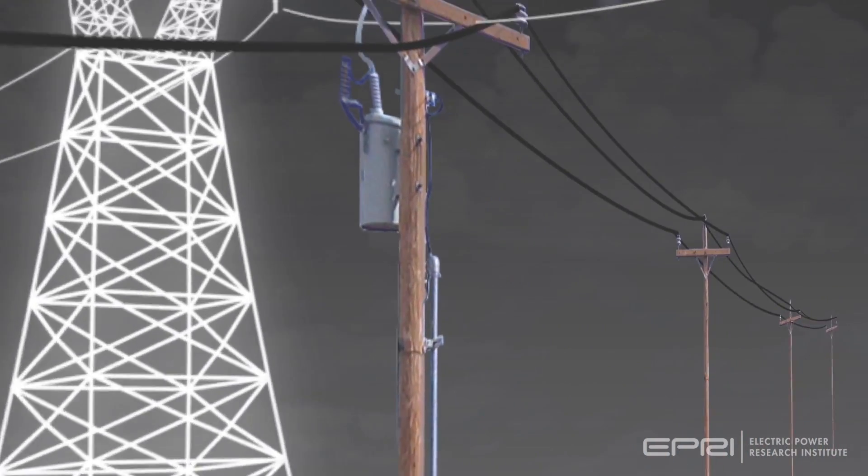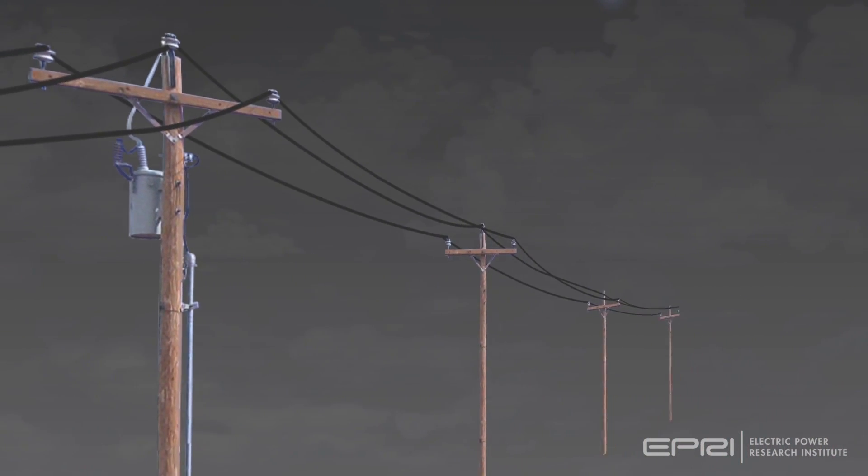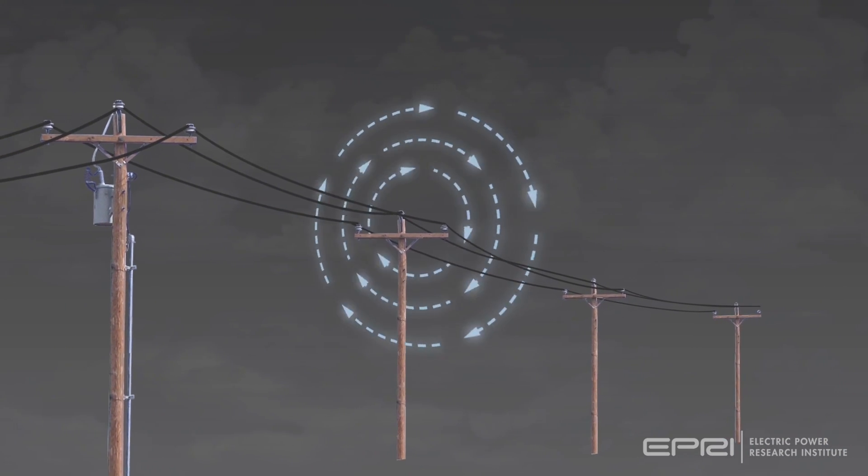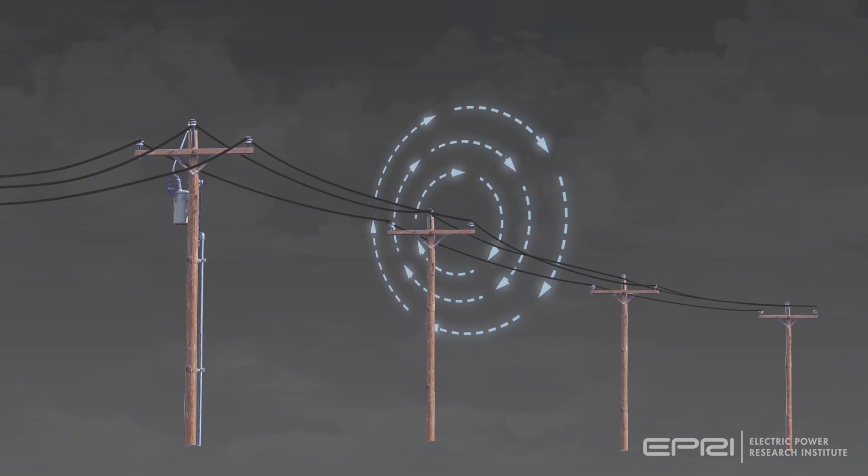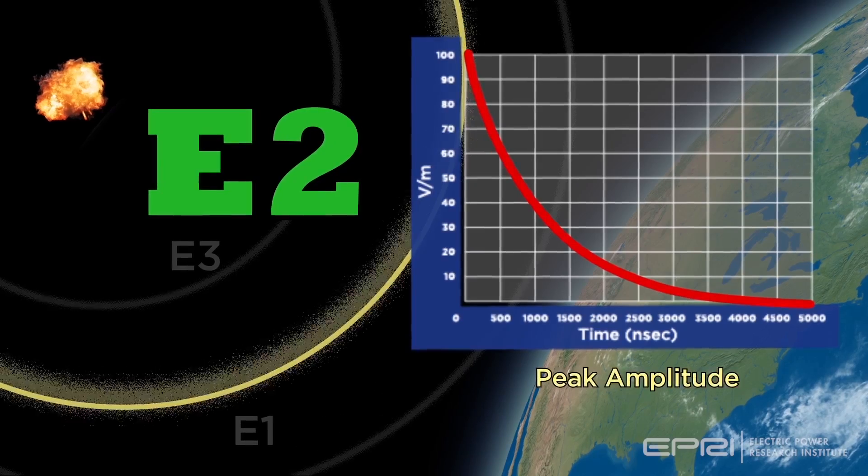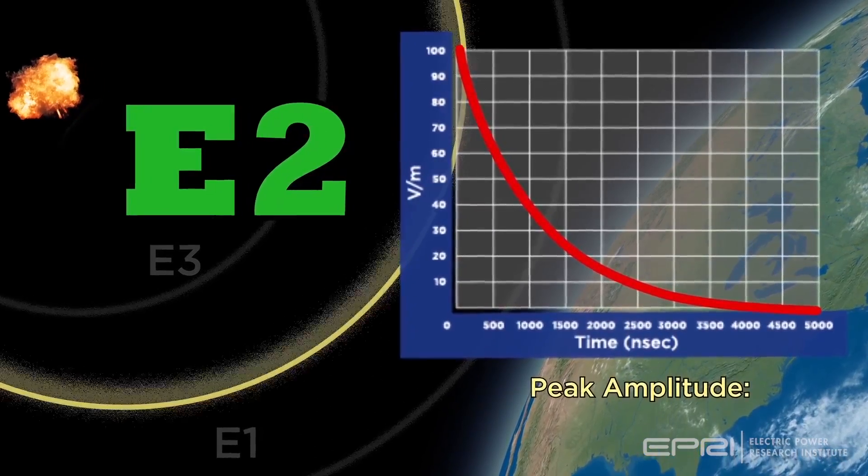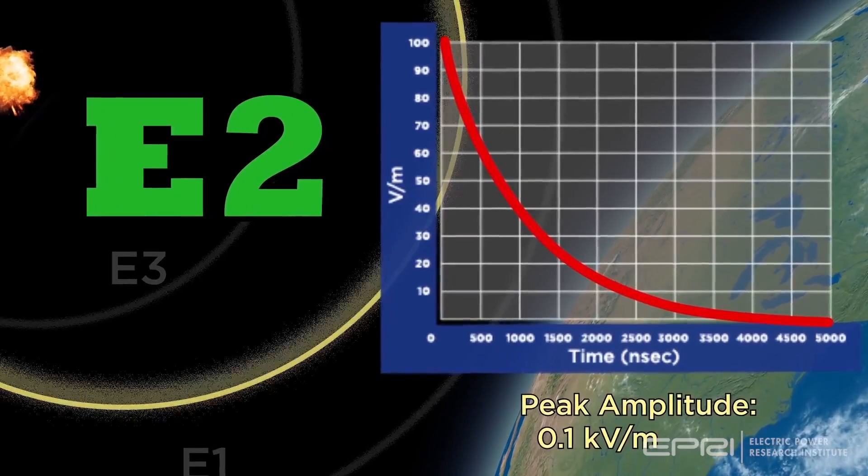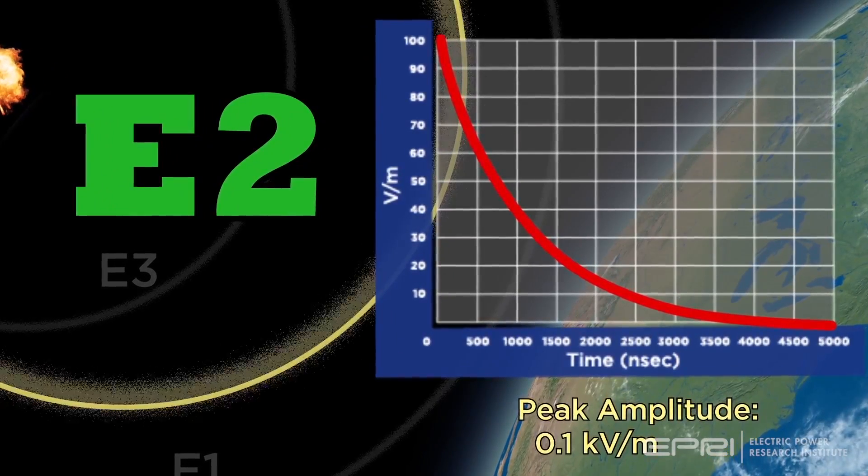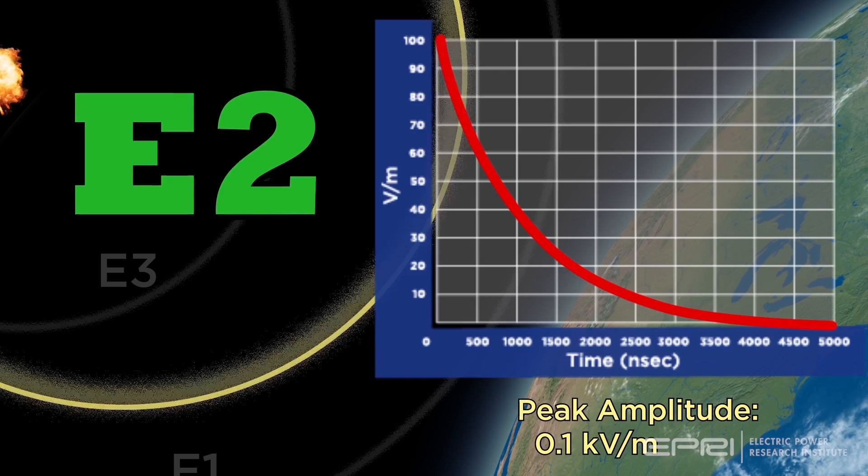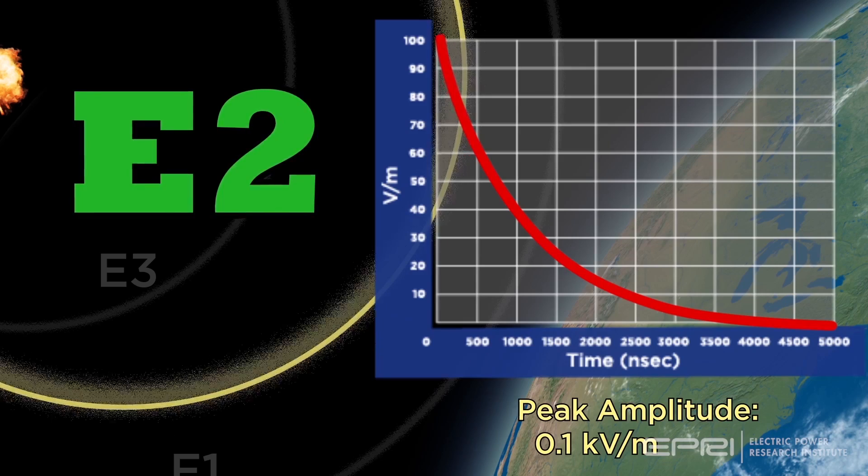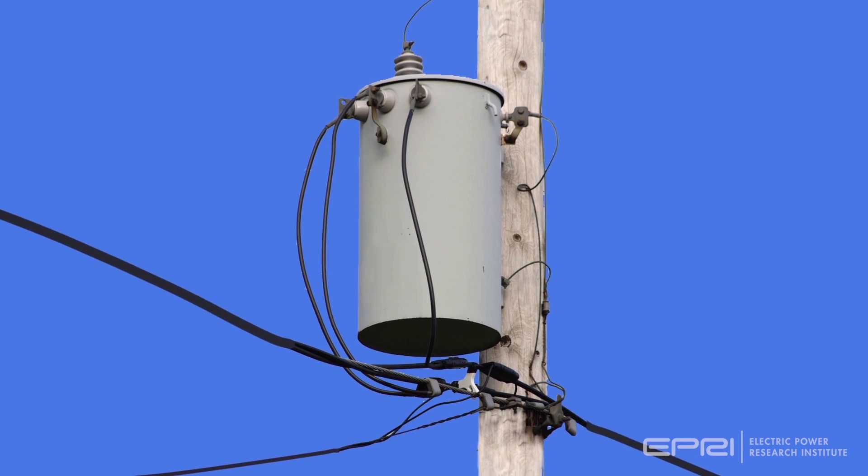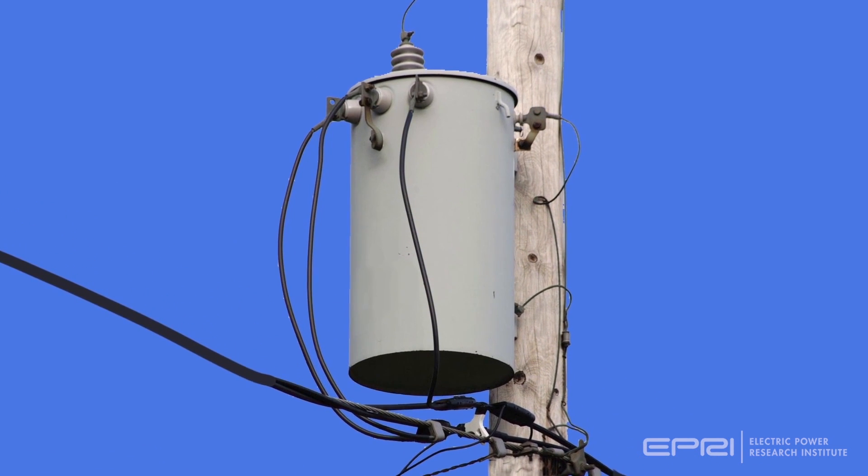But rather, it couples to electric infrastructure as a nearby lightning stroke would couple to a distribution line. Secondly, the peak amplitude of the E2 waveform has a peak amplitude of only 0.1 kilovolts per meter, far less than that of a typical lightning stroke and the E1 pulse that occurs immediately before the E2 pulse. As such, potential impacts to electronics and other power system components is expected to be minimal.